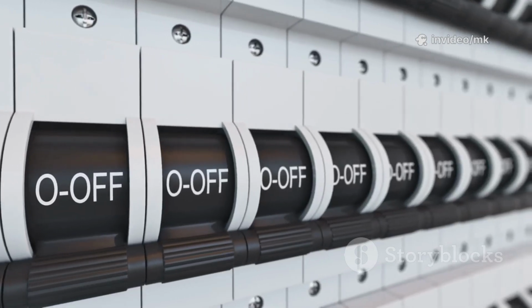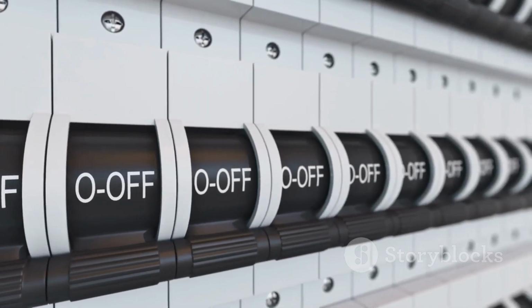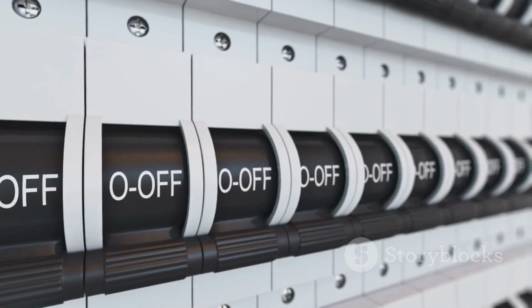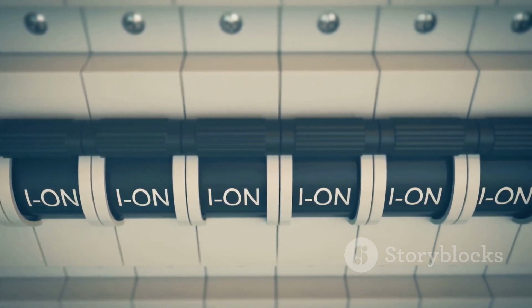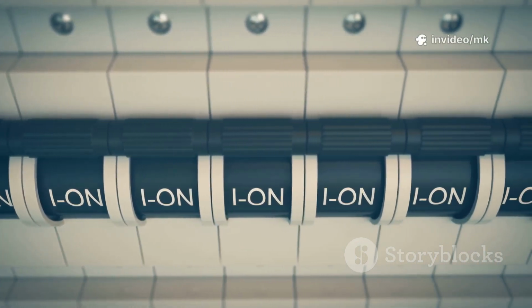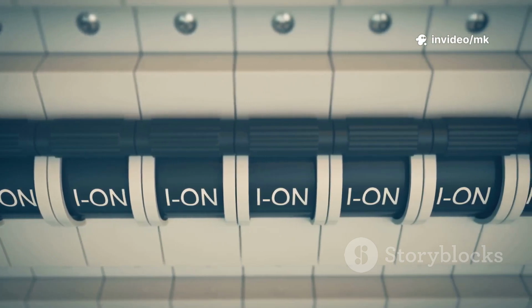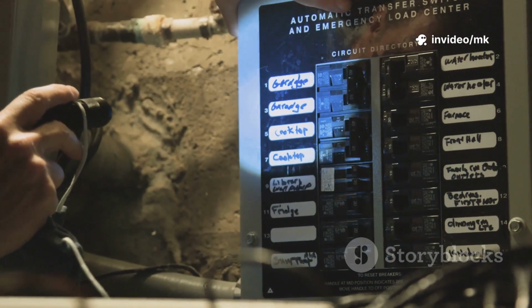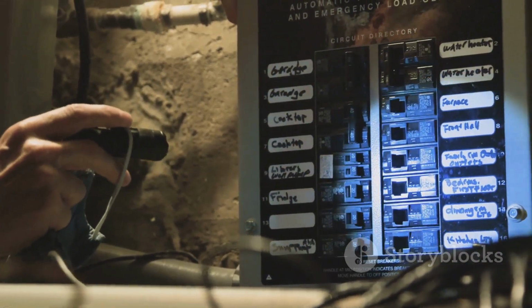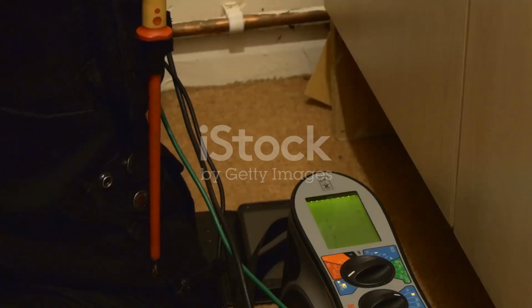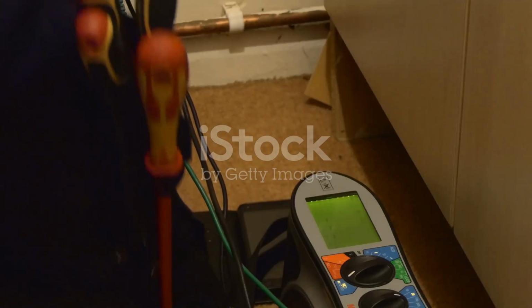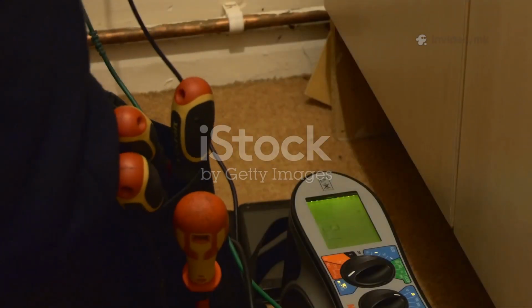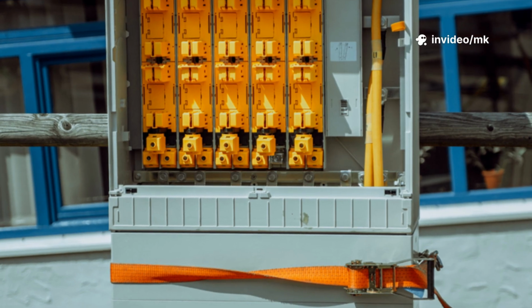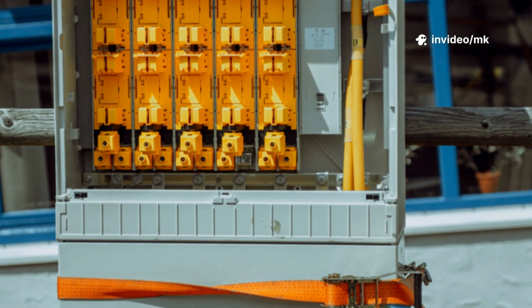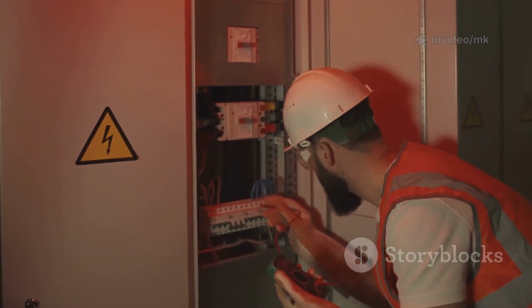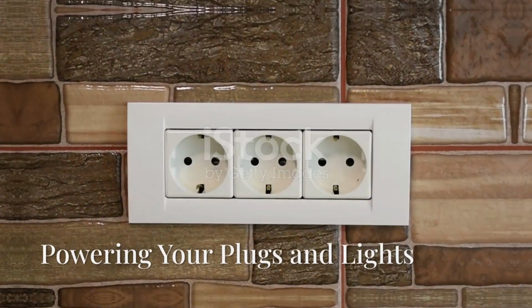The second type is the RCD, or residual current device, which protects you from electric shocks. It constantly compares the current going out and coming back. If there's a difference, it trips instantly, cutting the power. RCDs can detect even tiny leaks of current, acting much faster than MCBs. Some consumer units use RCBOs, which combine both functions for individual circuits. These devices are lifesavers and are standard in modern homes. Together, they keep your wiring and you safe.